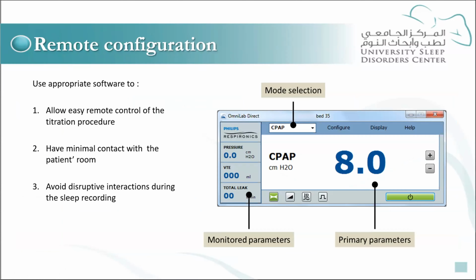What would be the next step? The next step is the use of the appropriate software. In this example, this is OmniLab Direct, which is the software that will provide you the ability to monitor your titration device remotely from the control room without going into the patient room. So it allows easy control of the titration procedure from your control room, reduces contact with the patient room, and avoids interactions which might disturb the patient during his sleep.